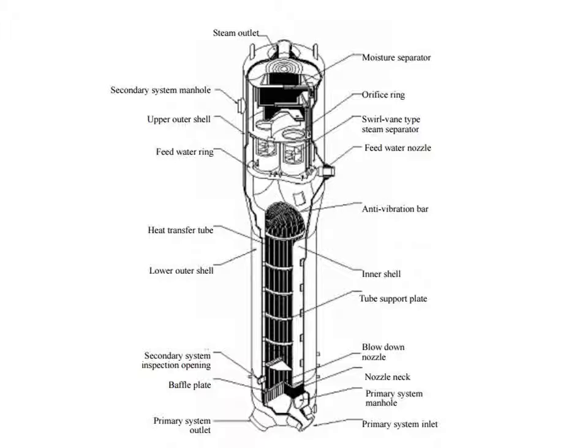As water in the primary coolant channel is pumped through the reactor vessel, it gains heat from the fission process occurring in the reactor. This hot water is then pumped to the steam generator, which acts as a large heat exchanger between the primary coolant channel and the secondary coolant channel. This means that the irradiated water from the core is kept separate from the electricity generating portion of the facility.